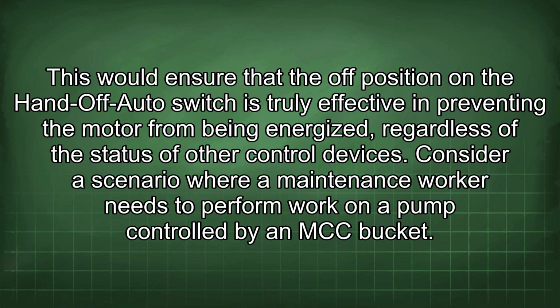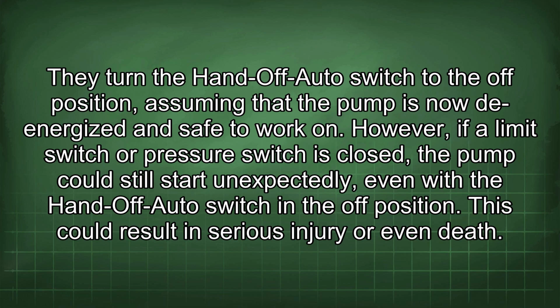Consider a scenario where a maintenance worker needs to perform work on a pump controlled by an MCC bucket. They turn the hand-off auto switch to the off position, assuming that the pump is now de-energized and safe to work on. However, if a limit switch or pressure switch is closed, a pump could still start unexpectedly, even with the hand-off auto switch in the off position. This could result in serious injury or even death.